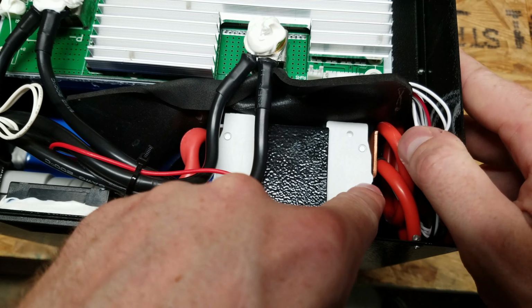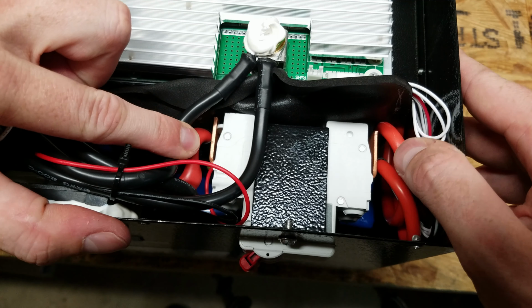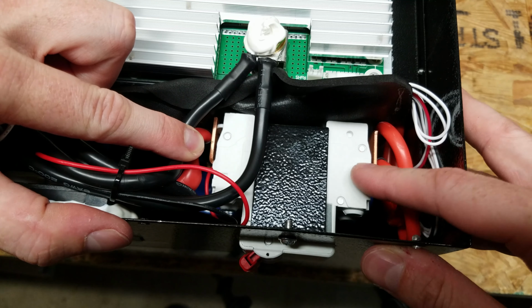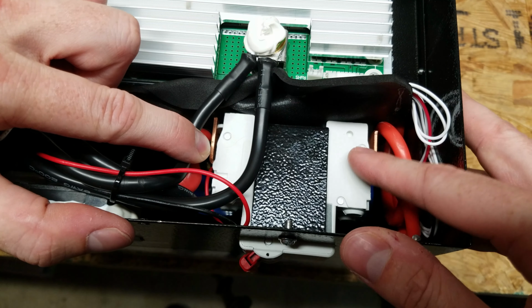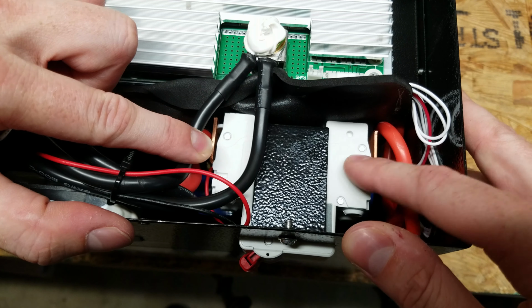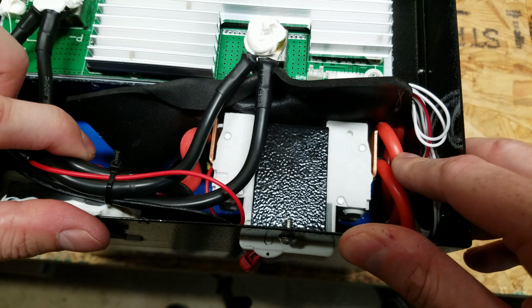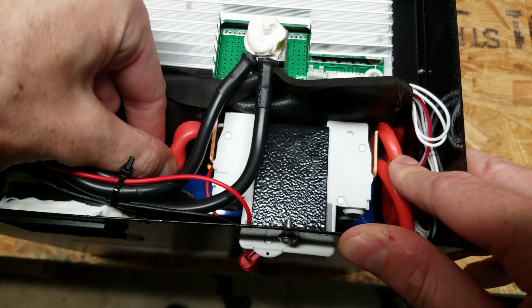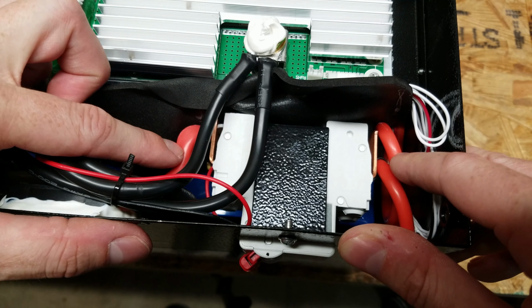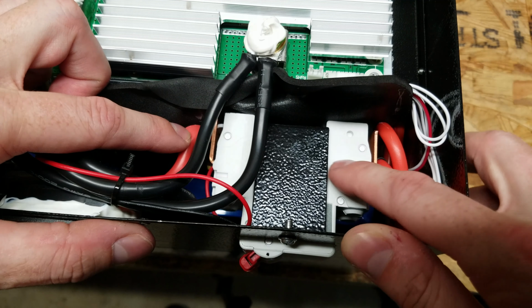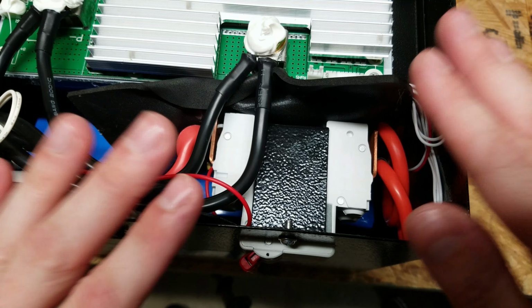However, there is a copper bar going on each side of the circuit breaker, so they are combining both poles. So it's 63 plus 63 amps, which gives you 126 amps. That's definitely an interesting setup, but it does meet the 80% derating rule of 100 amps continuous current, so this will work for 100 amps continuous current.